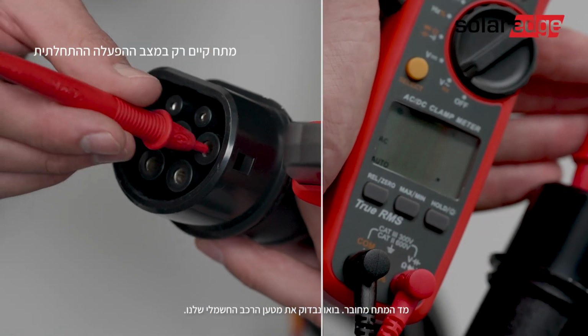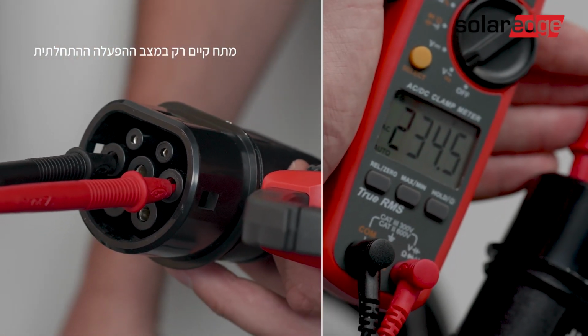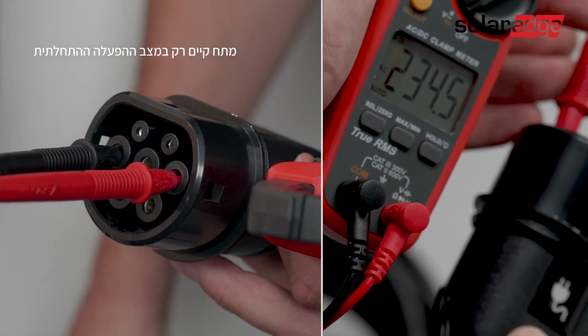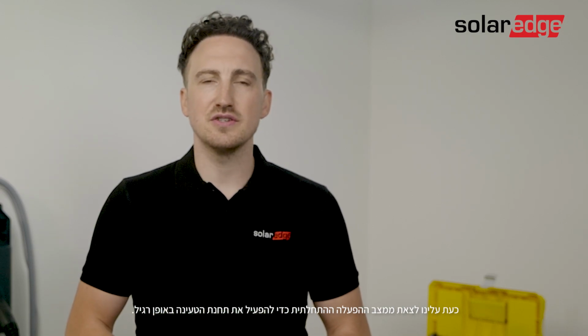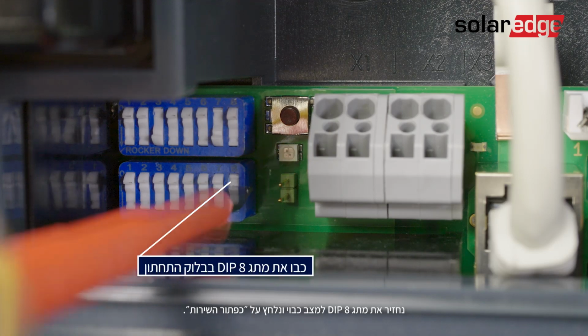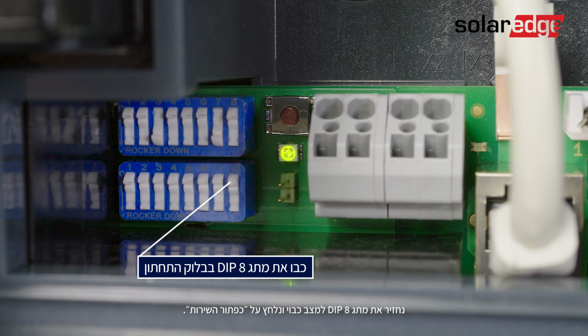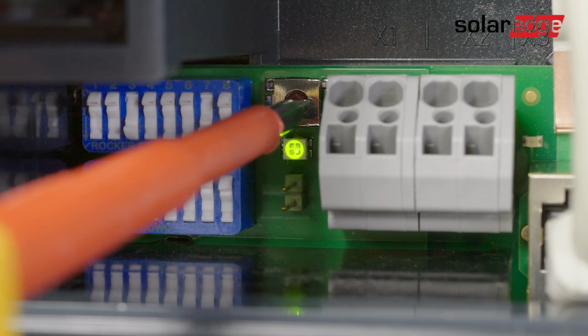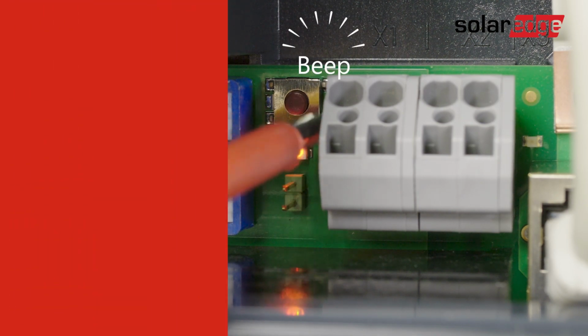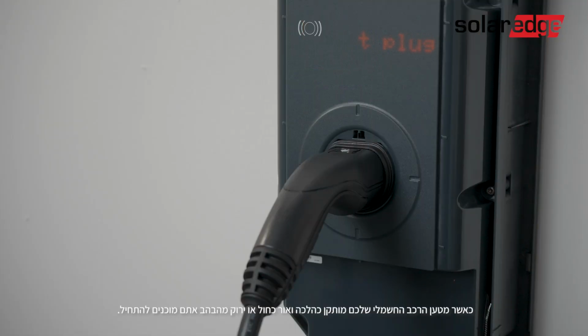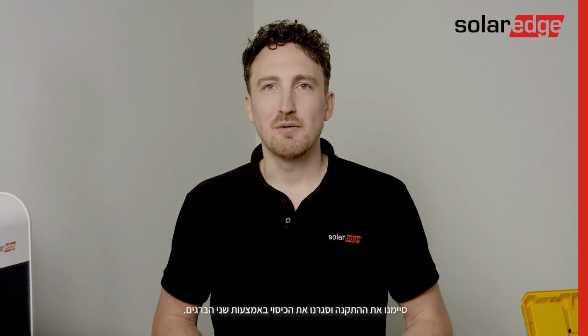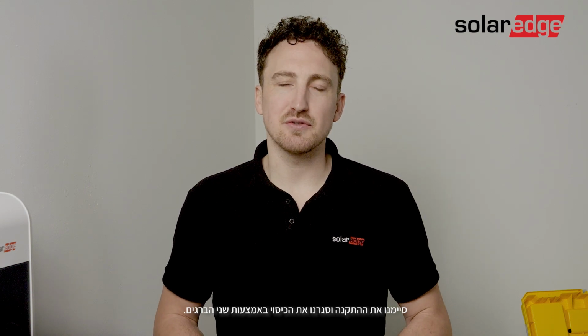Okay, voltage meter is connected. Let's test our EV charger. Yes, everything looks great. Let's move on to the next step. Now we'll need to deactivate the commissioning mode in order to operate the charge station properly. Let's set the dip switch 8 back into the off position, and now we're going to press the service button. Once your EV charger is properly installed and you have the blue or green LED blinking, you are ready to start. We finished the installation and closed the cover with 2 screws.